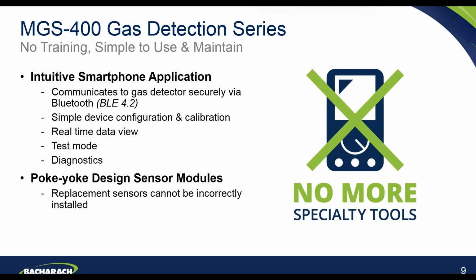From a user interface perspective, in the design of the 400 series we wanted to minimize training requirements and again keep it simple to use and maintain. Therefore, we developed an intuitive smartphone application. As I mentioned earlier, this is available today on both iOS and Android devices. It communicates via Bluetooth to the MGS-400 series detector. It essentially offers very simple configuration and calibration features. It offers a real-time data view of the current status of the sensor and the performance. It offers a test mode, so you can carry out some test functions on the outputs, etc. And it offers some diagnostic information around the sensor life, etc., that we'll go into in some more detail.